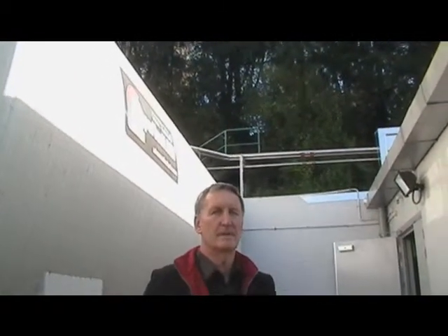And that 30 seconds standby power is delivered by gensets largely? Yeah, four gensets. So we'll start at the beginning here, and you've got your fuel supply. How much is this, for one generator? No, that's for 4 generators, the whole lot. 20,000 litres of diesel, and here we've got indication as to its status. Full tank, overfull, and then graduated. The light just came on now, just slightly below full.